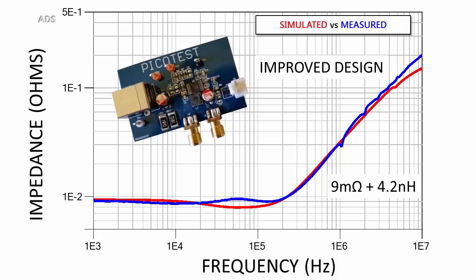Our improved design of this VRM is flat and can be represented as 9 milliohms and 4 nanohenries in a signal integrity simulator.